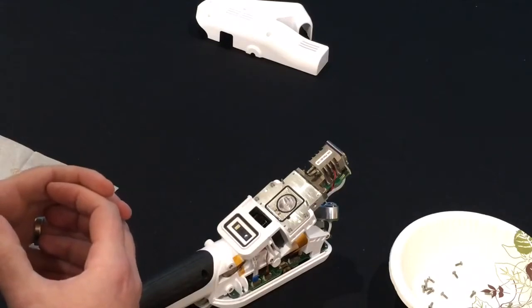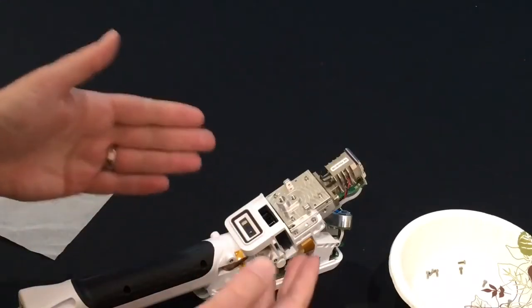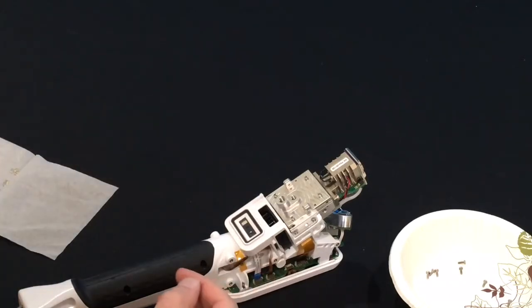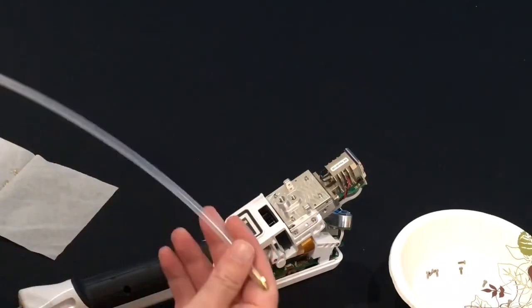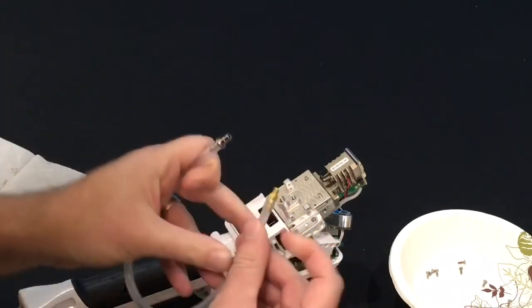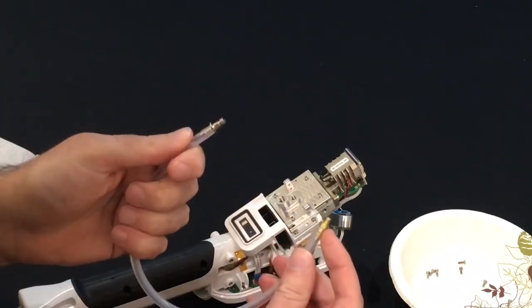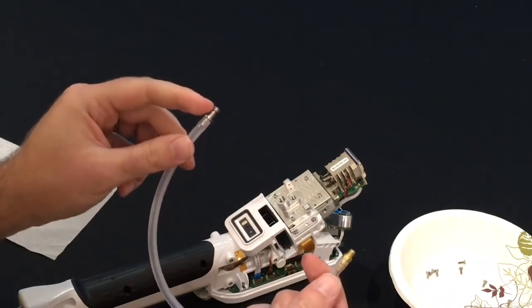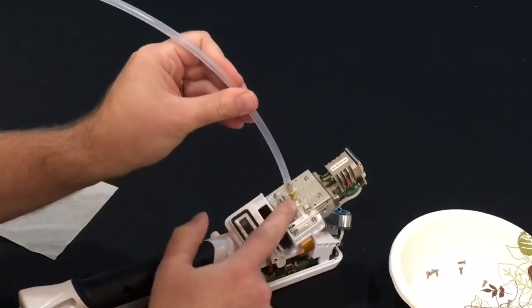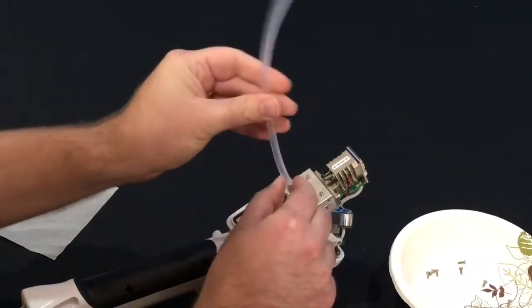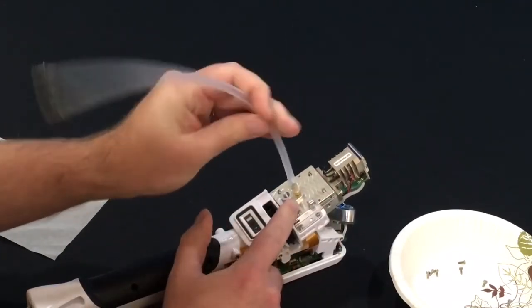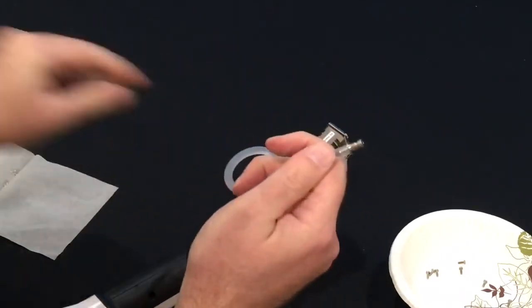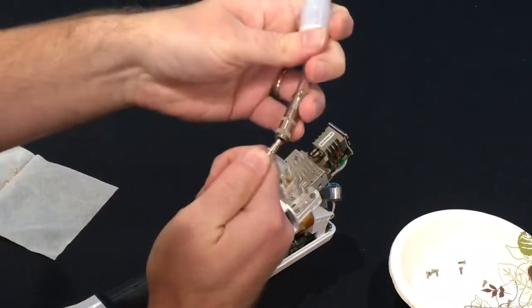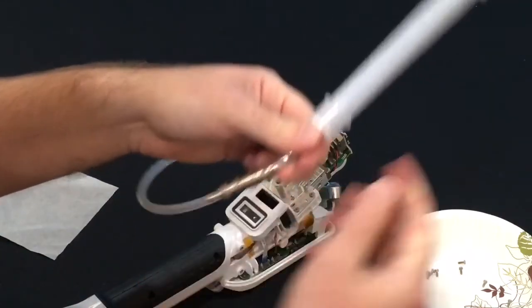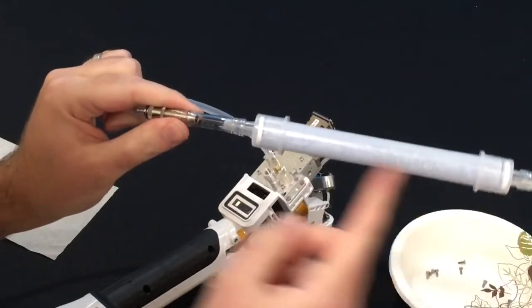the calibration process. Once you've replaced the pump cover and the filter cover, you'll next want to attach the zero kit using this length of tubing, which has a hose barb on one side, 10-32 hose barb, and a quick connect fitting on the other side. You will connect the hose barb into this smaller aperture here, like that. And then this quick connect fitting connects to the zero kit like this. So now we have air that's going to flow through our desiccant into our instrument.